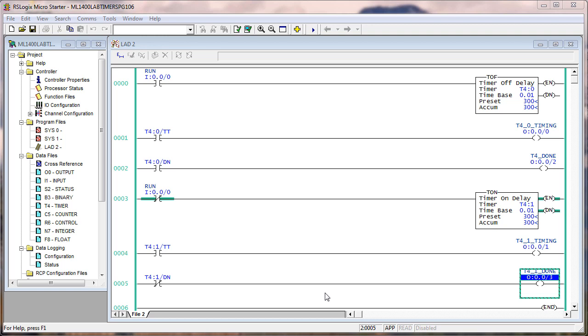Would you say that any use of the control bits or the accumulator register would yield the same results in logic? Yes, they would if you use the control bits like we did. Okay, we inverted the input that controls the timer, the TON, to make it behave like a TOF. And then we inverted the done bit to control an output.